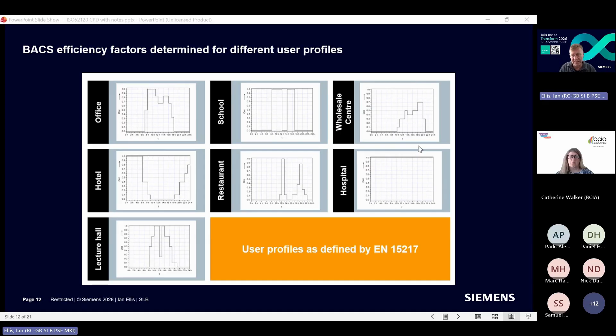By taking those two factors - the different classes and the different occupancy patterns - these are the figures the standard puts out as the potential energy savings you can get going from a Class C to a Class A design, or upgrading an existing Class C BMS to Class A. It is broad brush - you don't put in specifics like square meterage, number of windows, or level of insulation, it doesn't go down to that level. But it shows that if you change the control design from C to A, whether at design stage or in an upgrade or refurbishment, these are the sort of savings levels you can see.